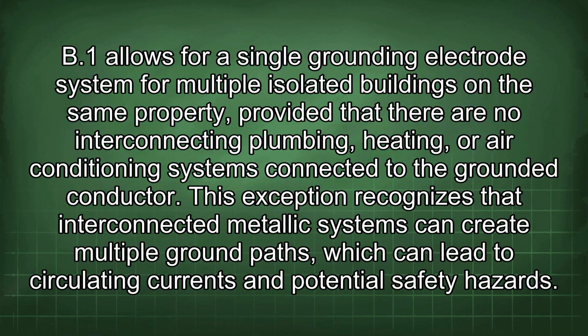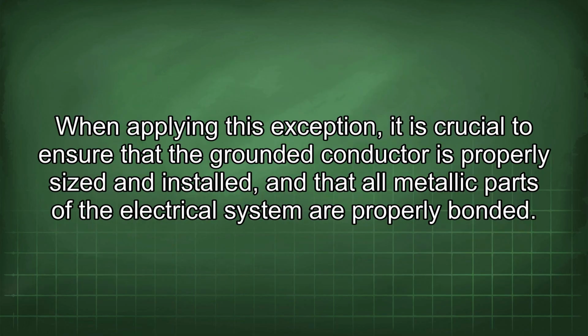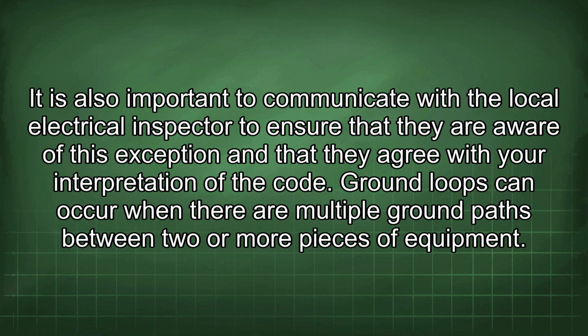This exception recognizes that interconnected metallic systems can create multiple ground paths, which can lead to circulating currents and potential safety hazards. When applying this exception, it is crucial to ensure that the grounded conductor is properly sized and installed, and that all metallic parts of the electrical system are properly bonded. It is also important to communicate with the local electrical inspector to ensure that they are aware of this exception and that they agree with your interpretation of the code.